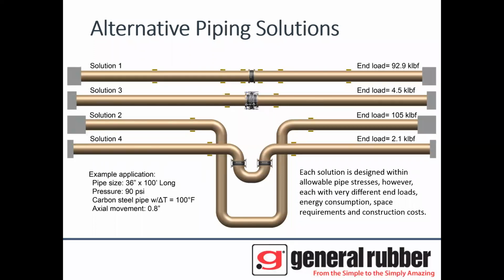Essentially, that is the pressure thrust force in the system, a relatively high force, but lower than if you didn't accommodate for the thermal movements. Solution 2 has a hard pipe loop, and while that piping holds back the pressure thrust force, and there's no pressure thrust force on the ends because the allowable pipe stress is high, it still has 100,000, more or less, 1,000 pounds of force on the ends.